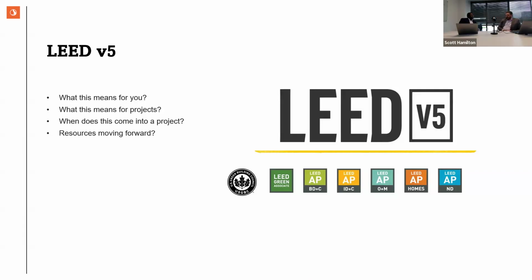Yeah, I think another important thing to note is that the acoustic requirements probably aren't changing that much. LEED itself never actually prescribed any new rating system or design standards. What they did was they deferred to other professional standards. So there's ANSI standards for schools. There was the FGI sound and vibration guidelines for healthcare. There's local municipality rules for environmental noise. All those kind of things play into them just saying, here are the professional standards, meet those, and you get the LEED credit.